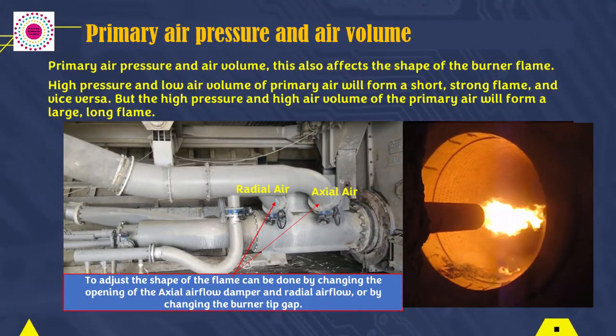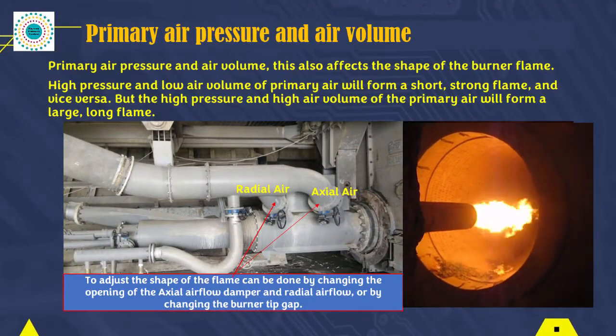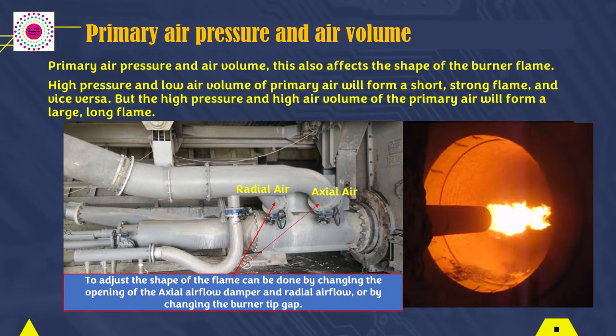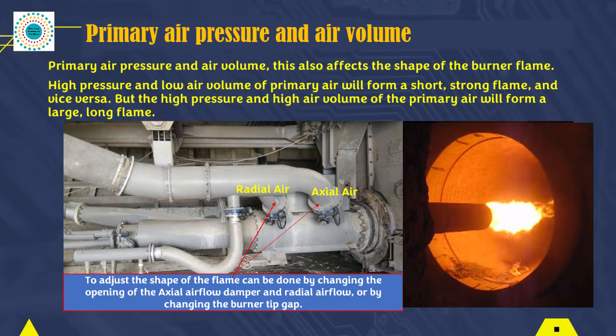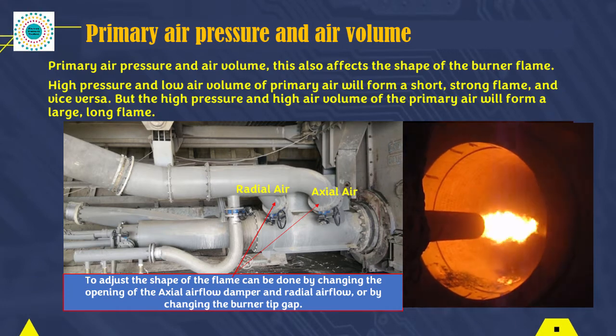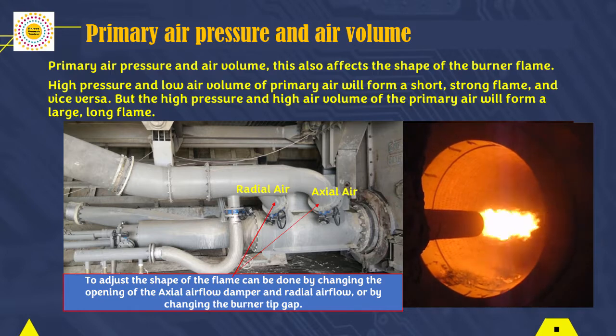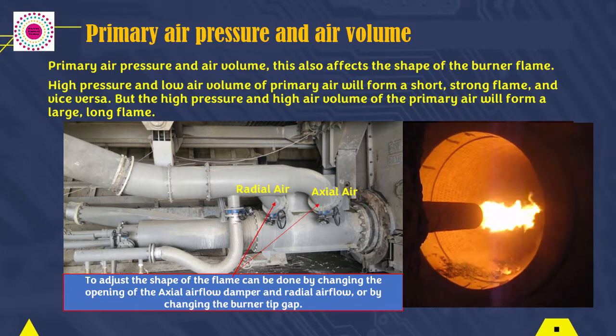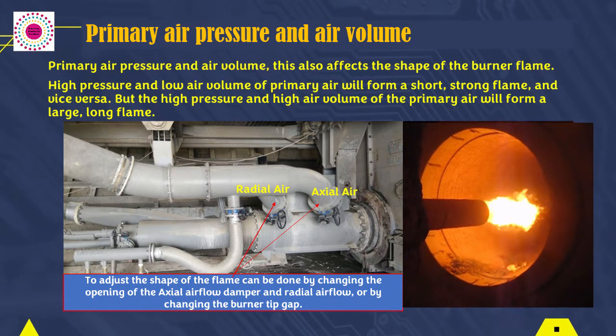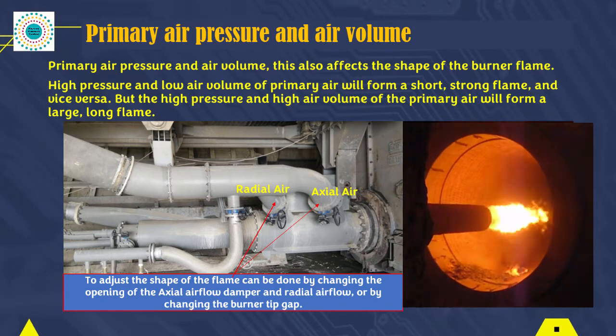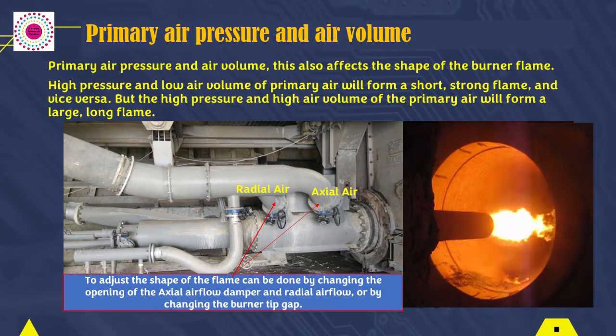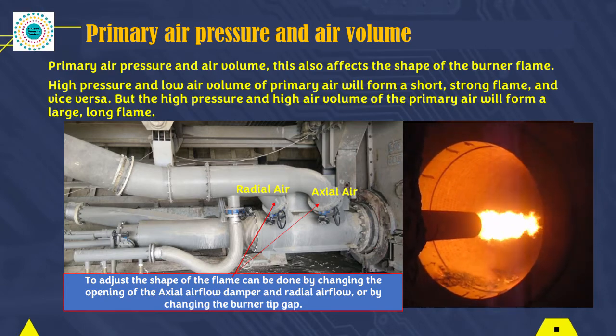Air pressure and primary air volume also affect the shape of the burner flame. High pressure and low volume of primary air will form a short, strong flame, and vice versa. But high air pressure and high air volume of the primary air will form a large and long flame. To adjust the shape of the flame, this can be done by changing the opening of the axial airflow damper and radial airflow, or by changing the burner tip gap.